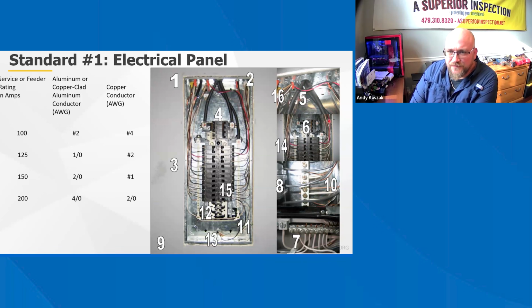Number 6, here in the middle, a means of disconnect for the service must be located either outside or inside the dwelling unit near the point of entrance of the service conductors. No more than 6 hand movements, or no more than 6 circuit breakers, may be used to disconnect all service. Typically, a main disconnect switch is required by the local authority. The main disconnect should be clearly marked to identify that it is the service disconnect.